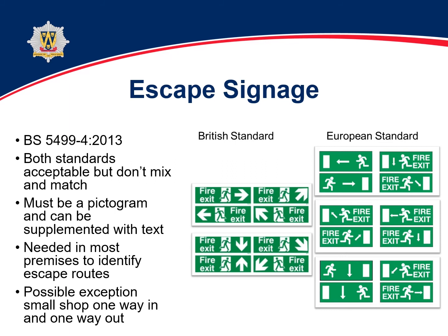So do you need them? Again, if you have one way in and one way out, a small shop, then probably no. If you have multiple ways in and alternative ways out, then yes. Another simple rule, which is in the British standard, you should be able to stand at any point in the building and see that one way in or one way out, or a fire exit sign directing you to the nearest available fire exit.